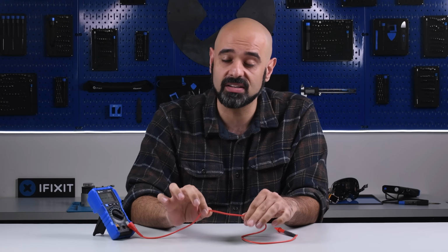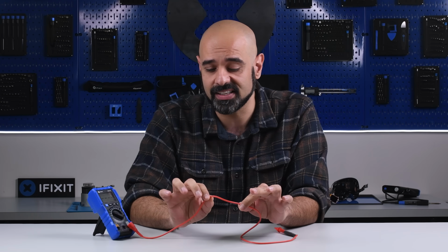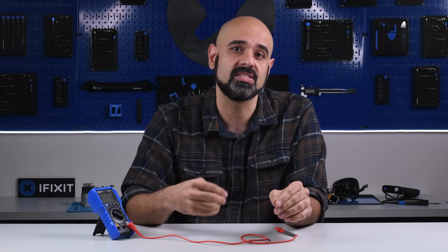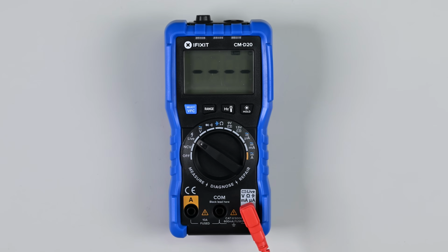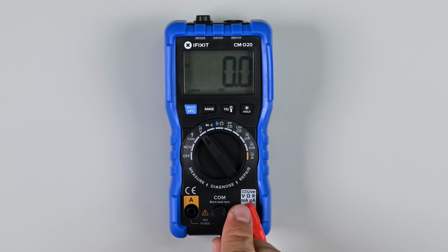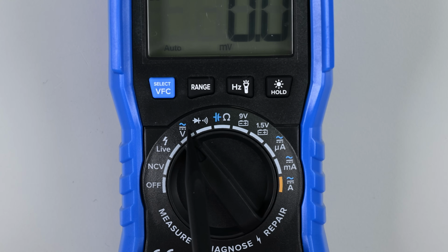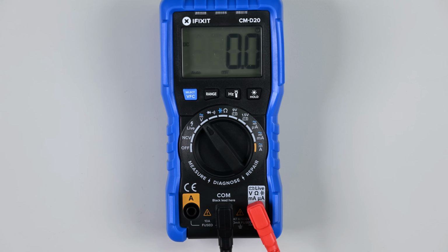You can also use it to see if there's a broken wire inside insulation, or to see which wires inside your junction box are hot. The next setting puts the multimeter in voltmeter mode, indicated by the white V symbol, meaning we can measure the voltage potential between 2 points. The solid and dashed white lines above the V indicate that we're measuring DC voltage as opposed to AC voltage. DC mode is the default setting on this multimeter.